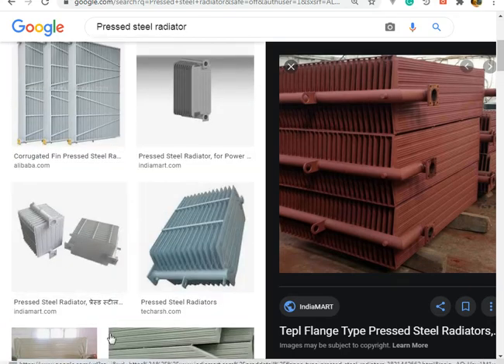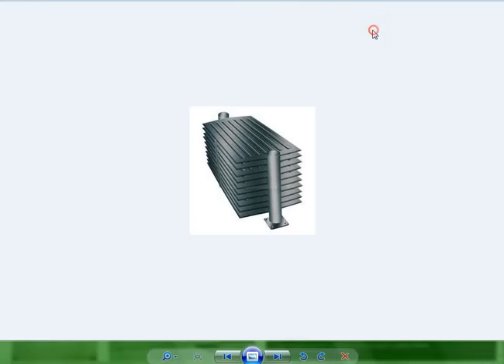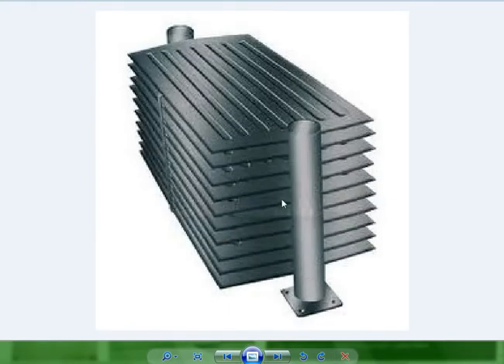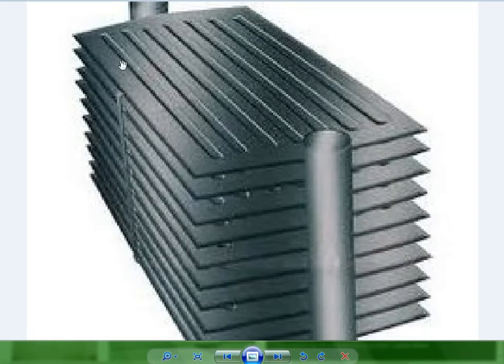What is happening inside this one? Look closely at this diagram. You have 1, 2, 3 inlets, and you can see there are 3 outlets also. This is the inlet of the pipe, and this is the outlet. This whole structure is attached along the height of the transformer tank, and it takes oil from the topmost point, and the oil flows through this channel, this channel, this channel, and so on through each channel.